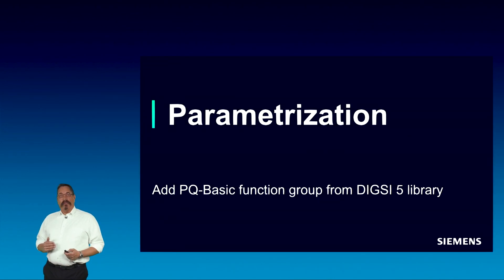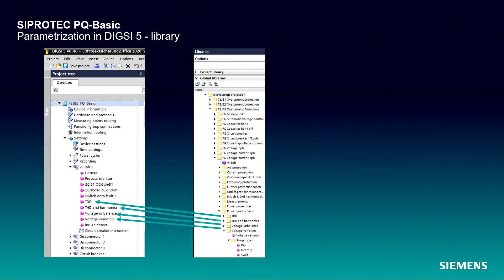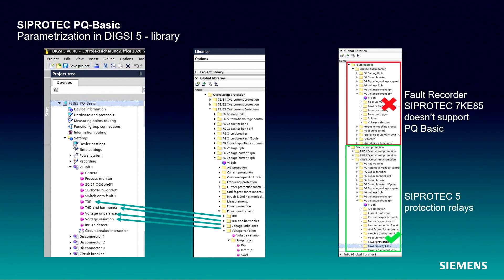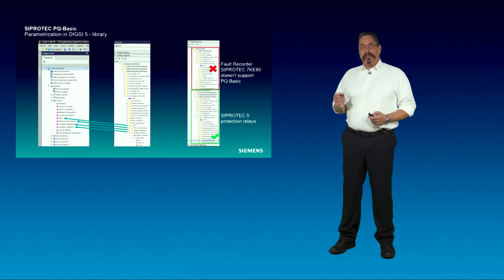Select PQBASIC function groups from the DIGSI 5 library. The DIGSI 5 library provides, inside the measurement function group, all functions related to PQBASIC. You have to drag and drop the functions into your device. PQBASIC is available for all SIPROTEC 5 protection relays with firmware 8.40 onwards. The new SIPROTEC 5 compact device can be equipped with PQBASIC as well. In the Fault Recorder 7KE85, PQBASIC is not implemented because this device already covers several measurement functionalities.